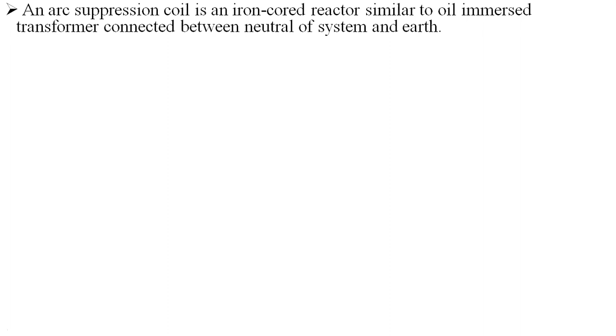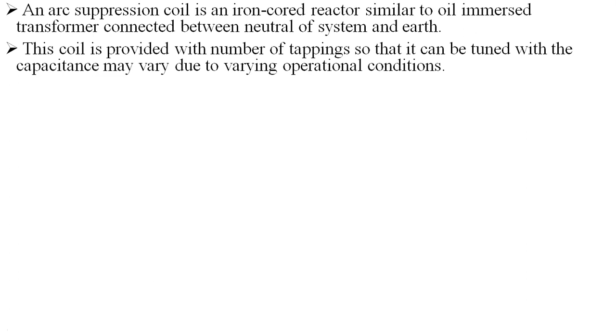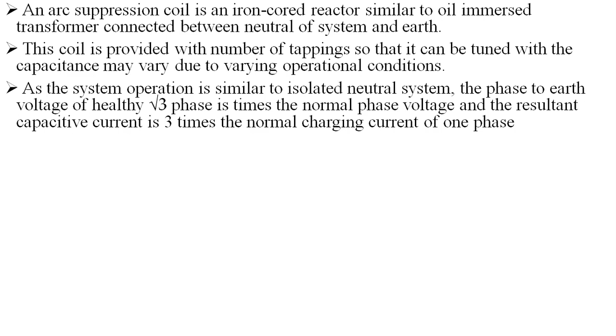An arc suppression coil is an iron core reactor, similar to an oil immersed transformer, connected between the neutral of the system and earth. This coil is provided with a number of tappings so that it can be tuned with the capacitance, which may vary due to varying operational conditions. As the system operation is similar to an isolated neutral system, the phase to earth voltage of the healthy phases is root 3 times the normal phase voltage, and the resultant capacitive current is 3 times the normal charging current of one phase. The resultant capacitive current leads the faulty phase voltage by 90 degrees, while the fault current lags the faulty phase voltage by 90 degrees.